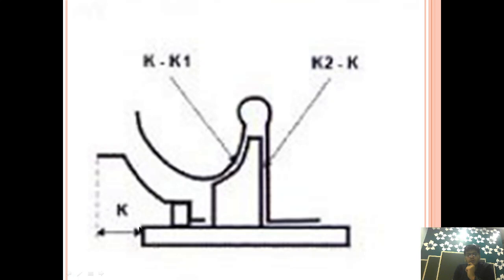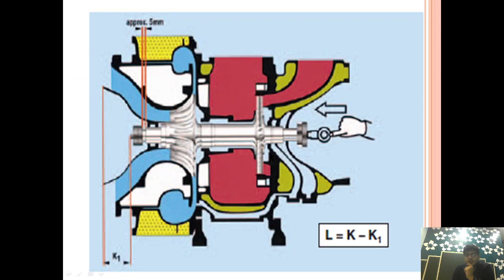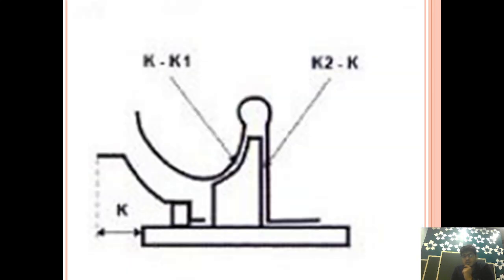We have taken the earlier K value during normal running. Now after pushing the rotor to the maximum on the turbine end, we are getting a clearance on the front part of the compressor and casing — this value is called L. The value K1 we are getting at this pushed position will be less than K, so K minus K1 gives us L. This is very clear.